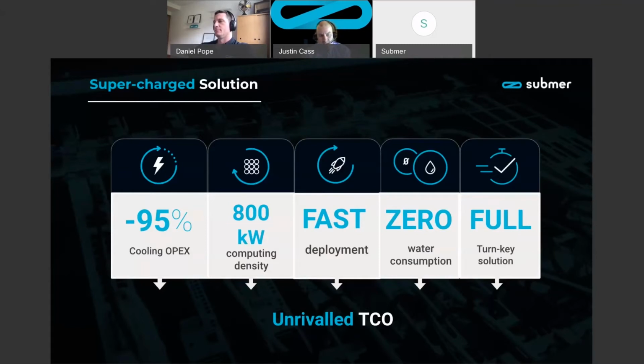With air cooling, especially in a containerized modular system, you have to deal with ambient temperatures as well as temperatures inside your container or modular data center. If it's really hot outside, it's going to be really hot inside. Suddenly you're changing air from 100 degrees down to 60 degrees to blow across your IT equipment, and that takes a tremendous amount of energy.